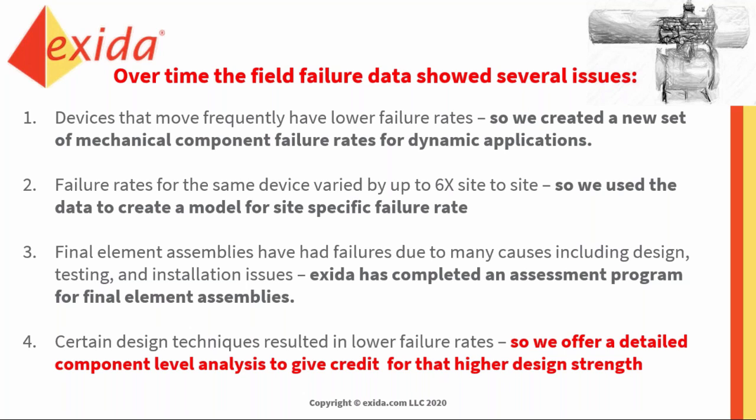The next complication we always come into play is that when you put final elements together as an assembly, they don't always work how you think they are. Some people just pick a random valve, a random actuator, a random solenoid, throw them together and hope they work. Well, other people do a complete torque analysis. They design the mounting and coupling with FEA and not just scrap metal. So we have a program on that now too.